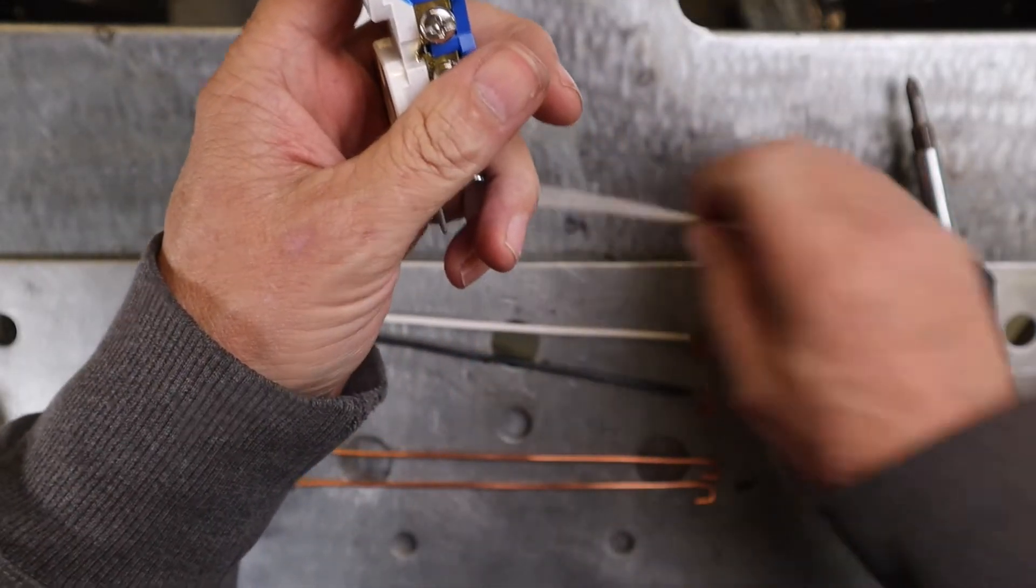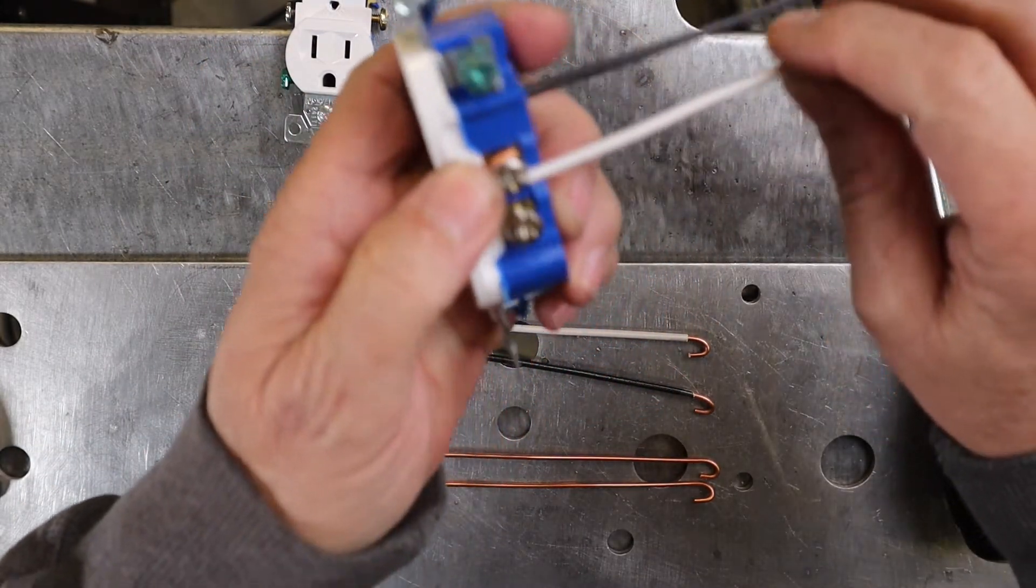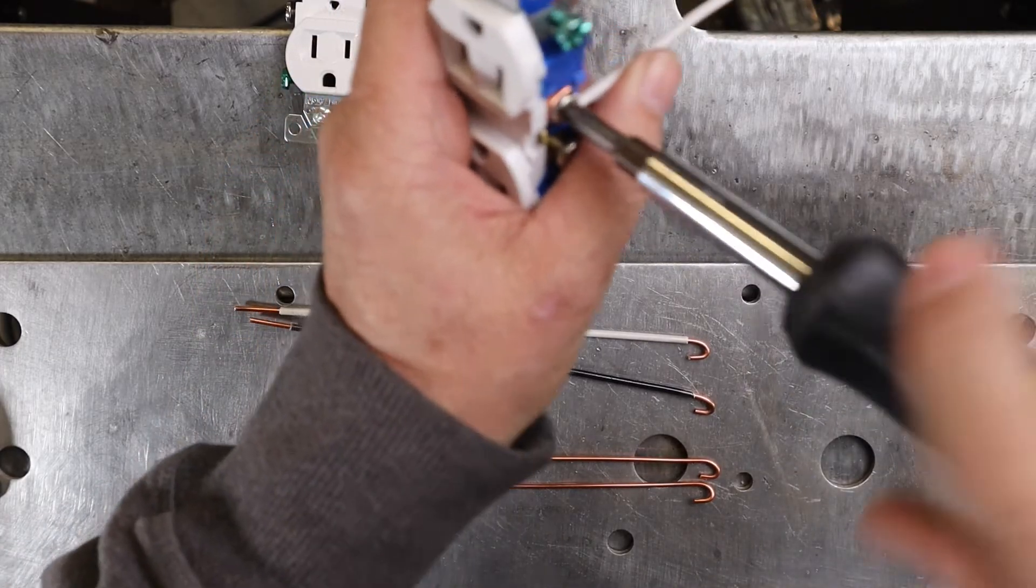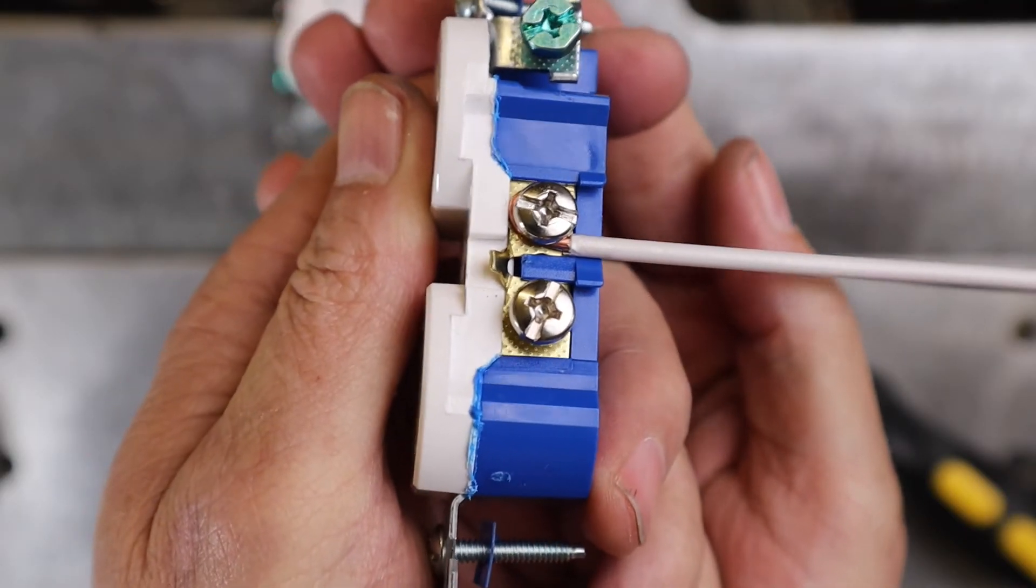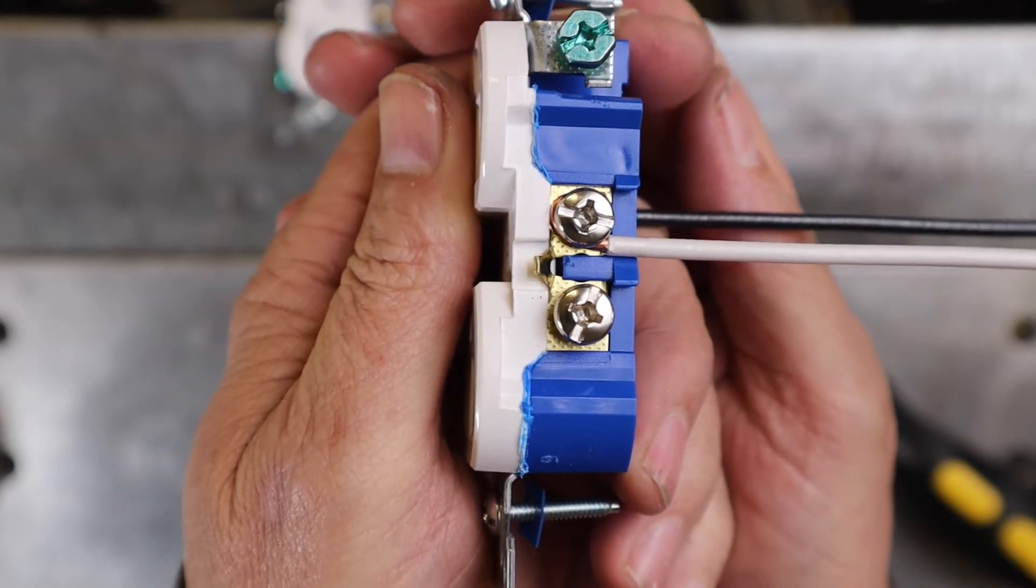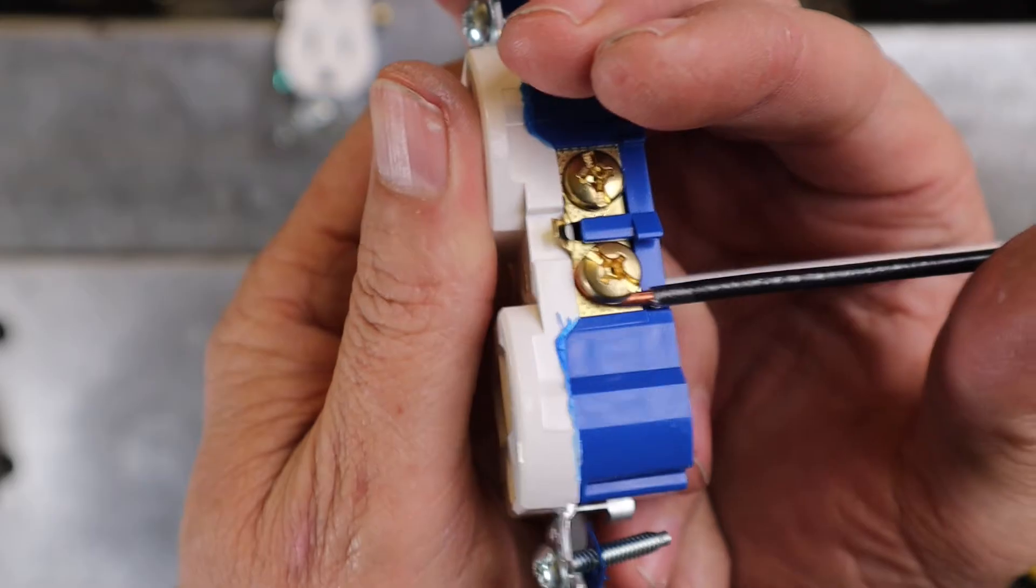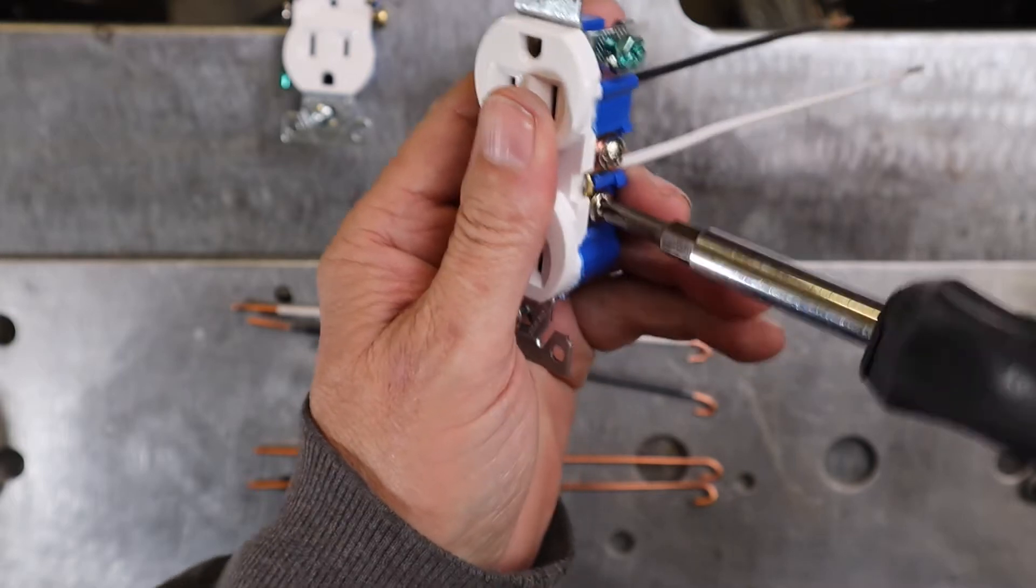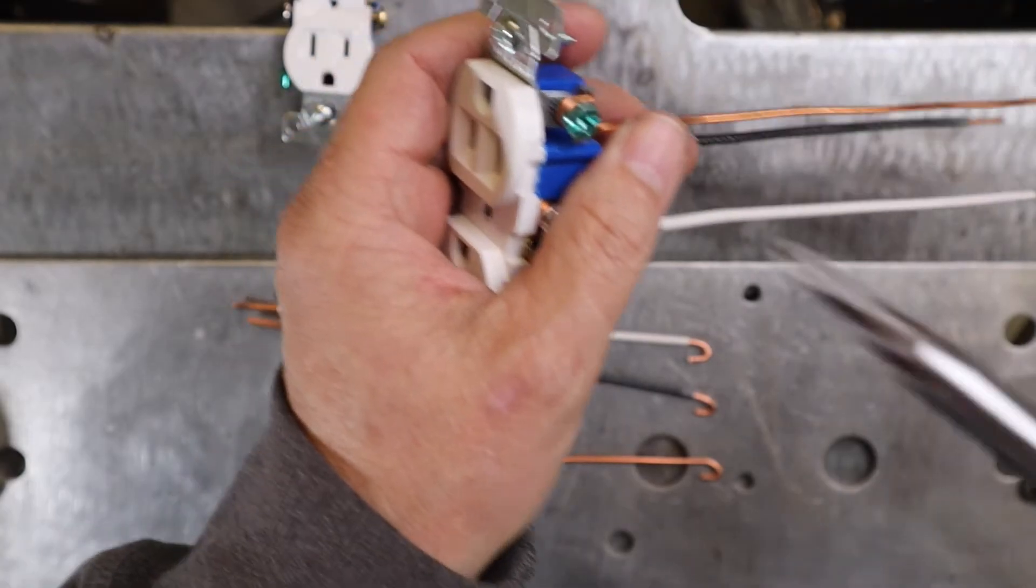Do the same thing for the neutral on the silver screw. See how that insulation is not underneath the screw? The screw is only touching on the copper wire, so that's how you want your strip to look once it's underneath the screw. Otherwise you could get a hot spot and cause you problems. Same thing with the hook going the same direction that the screw goes.